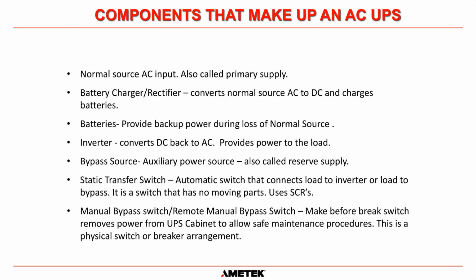And then, not to be confused, the static switch should never be confused with the manual bypass switch or the remote manual bypass switch. The static switch is electronic and has no moving parts, but the manual bypass switch, or remote manual bypass switch, is a make-before-break mechanical switch that removes power, usually from the UPS cabinet, to allow safe maintenance. This can be a rotary switch or a breaker arrangement, depending on the manufacturer of the UPS you have. But for AMETEK Solid State Controls, it is most of the time a rotary switch.